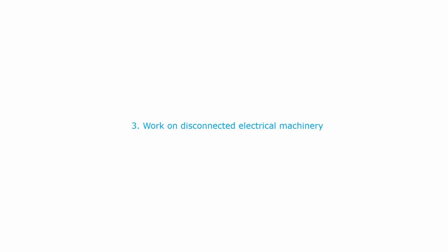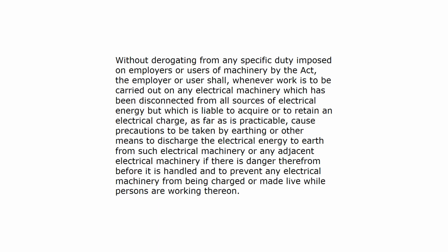Work on disconnected electrical machinery. Without derogating from any specific duty imposed on employers or users of machinery by the Act, the employer or user shall, whenever work is to be carried out on any electrical machinery which has been disconnected from all sources of electrical energy but which is liable to acquire or to retain an electrical charge, as far as is practicable, cause precautions to be taken by earthing or other means to discharge the electrical energy to earth from such electrical machinery or any adjacent electrical machinery if there is danger therefrom before it is handled, and to prevent any electrical machinery from being charged or made live while persons are working thereon.